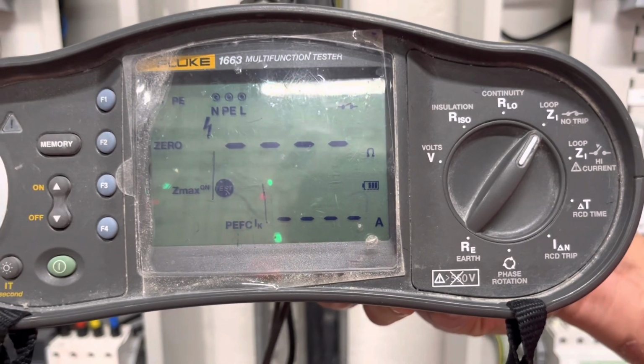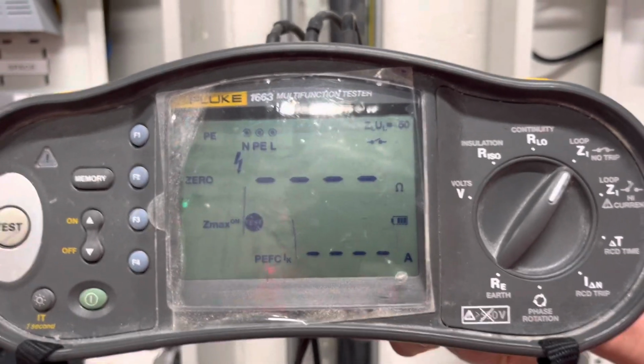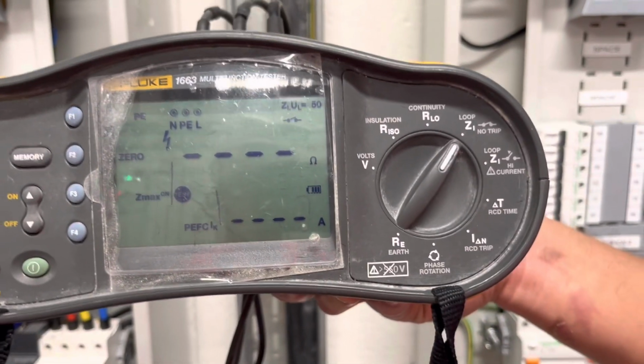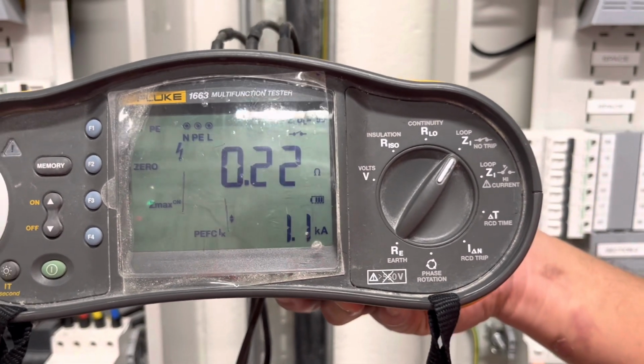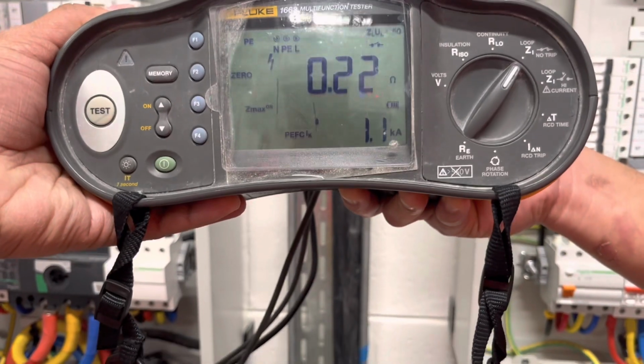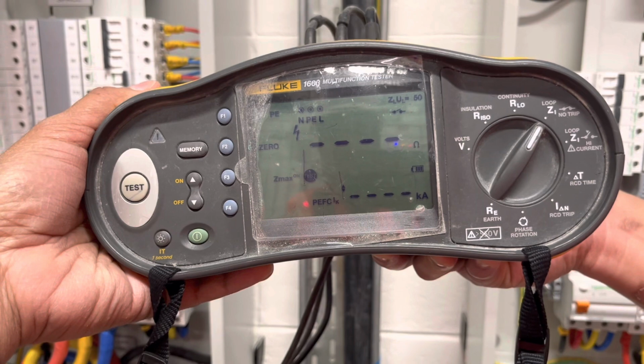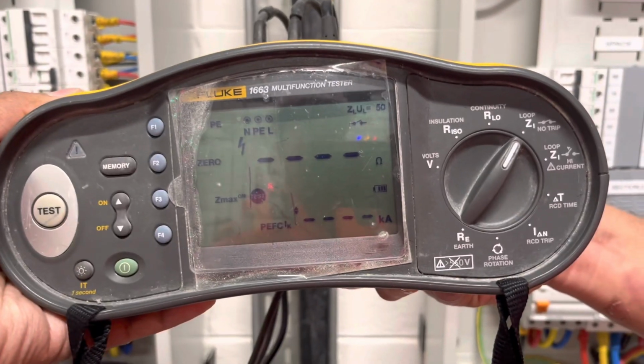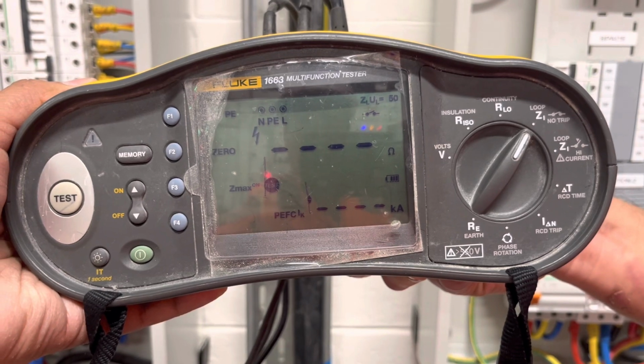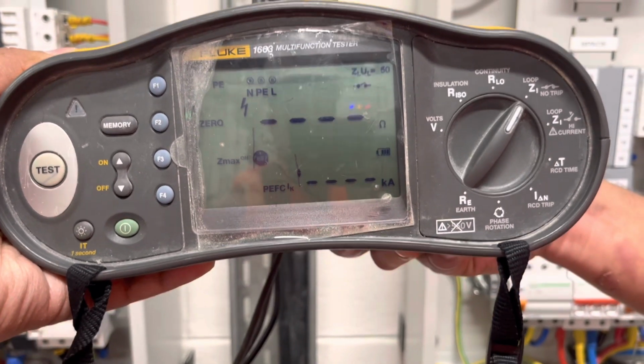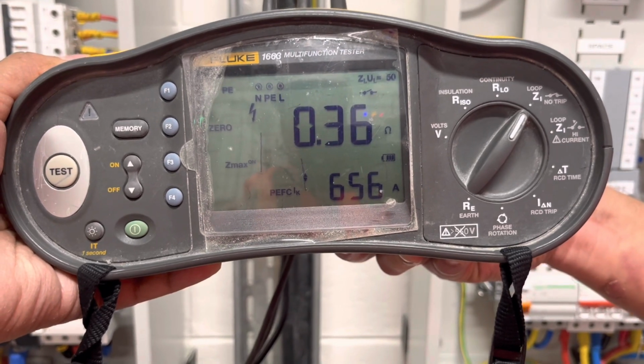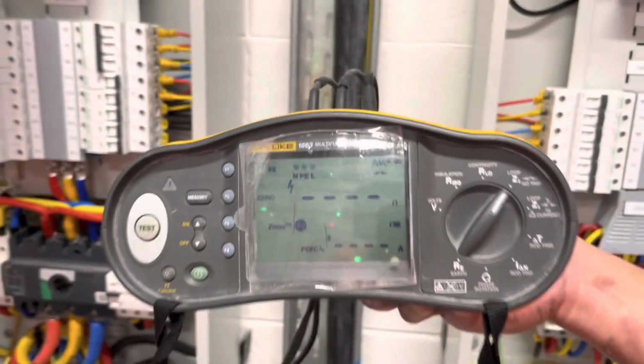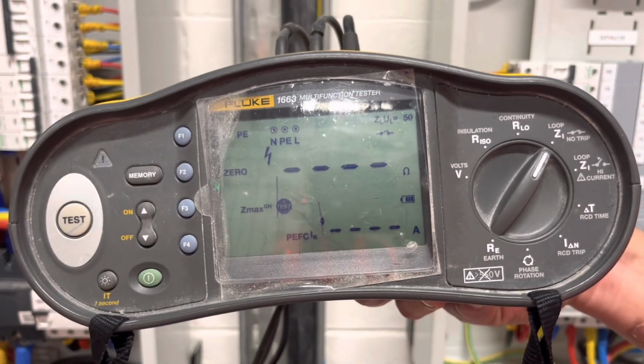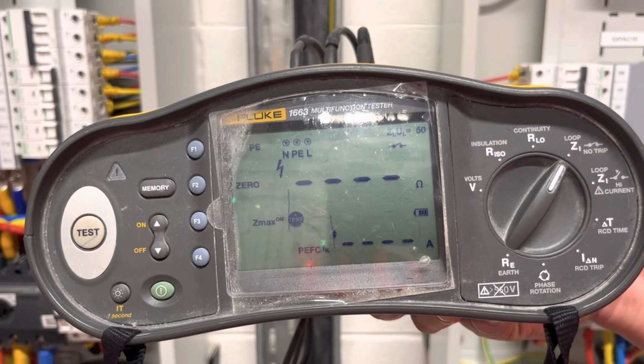We'll take time, guys. Okay, 0.22. 0.22 is good enough. Okay, the impedance of the line. The other one is yellow. It will not be above 1; the impedance of that cable is good enough. 0.36 ohms, okay. And the blue, 0.32. Okay, and so we will go now to the trip test.